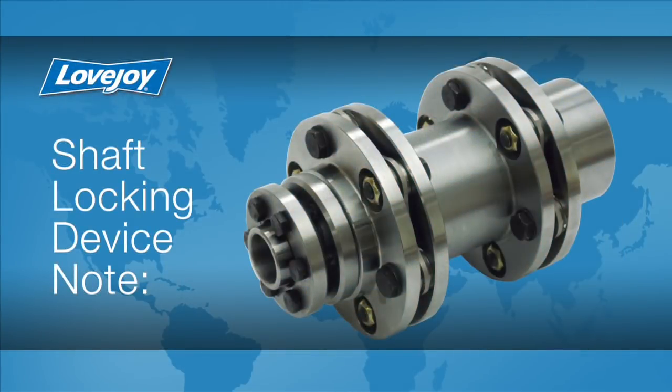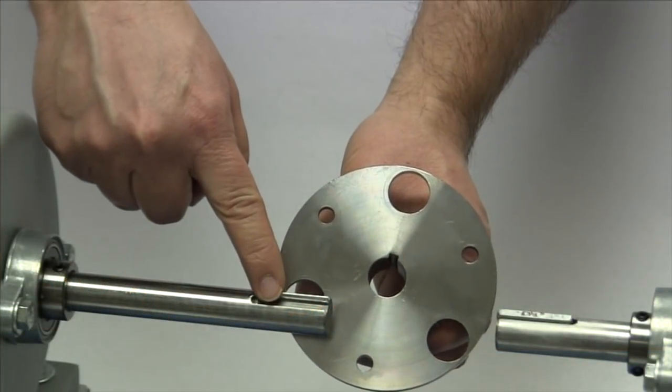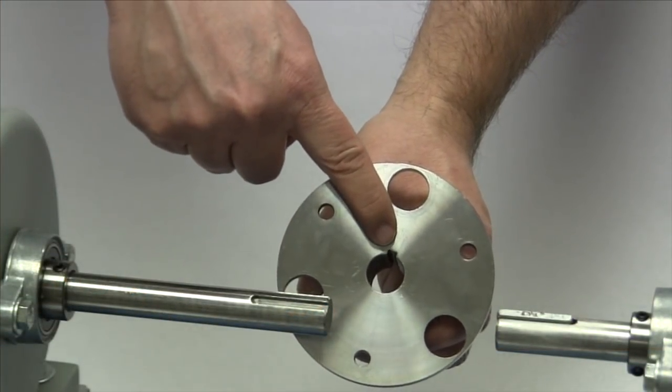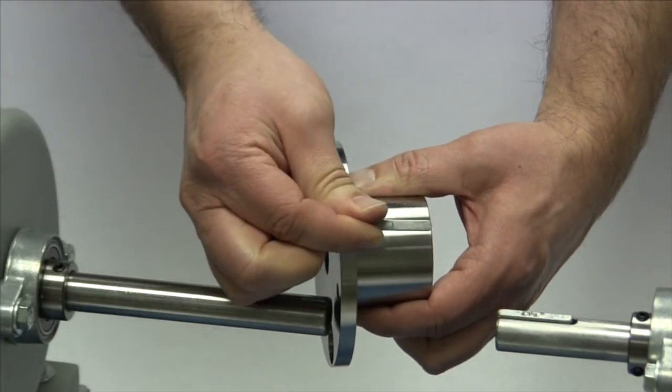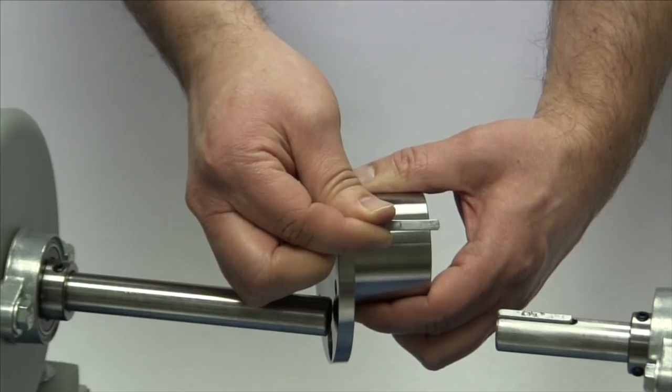Except in applications where a Lovejoy SLD or shaft locking device is used, both shafts and hubs should have keyways. To accommodate dynamic balance and allow for maximum torque transmission, the length of the key should always match the length through bore of the hub.